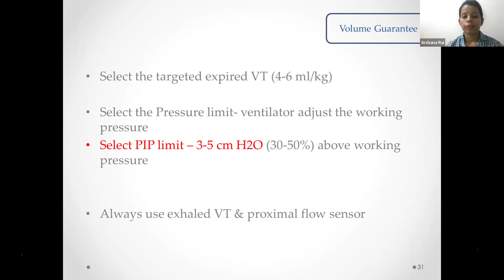And why VTV doesn't fit all with the same size: we have to target this expired tidal volume as per the patient's condition. This can be calculated based on the infant size, various pulmonary diagnoses the patient is having, and the modes we are using. Like the smaller the baby, there will be more dead space because of the instruments like the flow sensor and all. So we have to set a higher tidal volume. And when the baby is older, like more than 2 weeks old, because of the physiological tracheomegaly, there will be more leak. So we have to set a high tidal volume in that also.